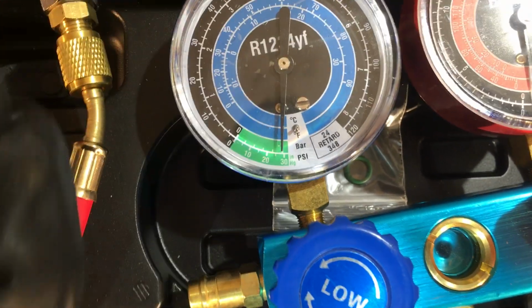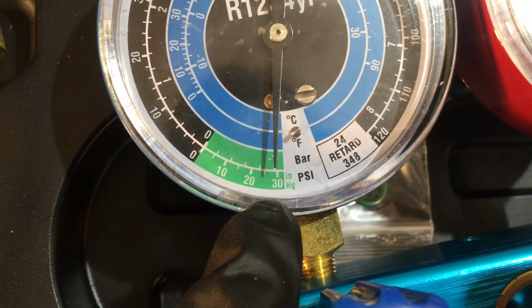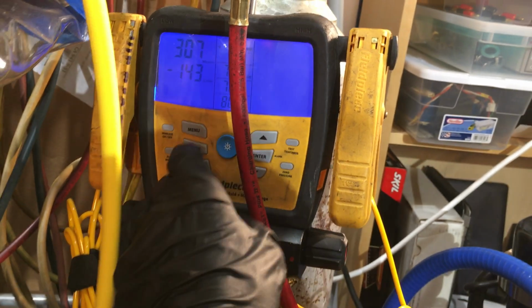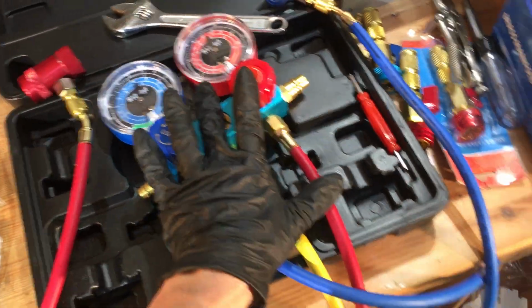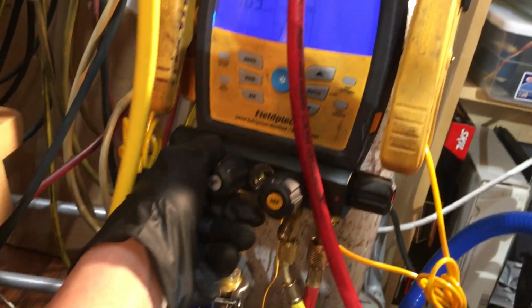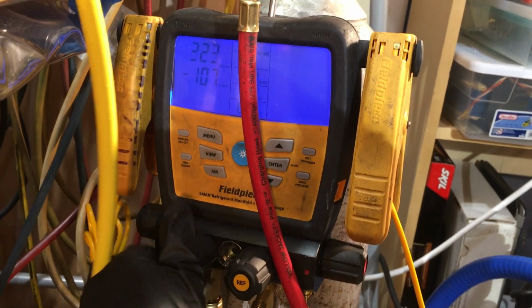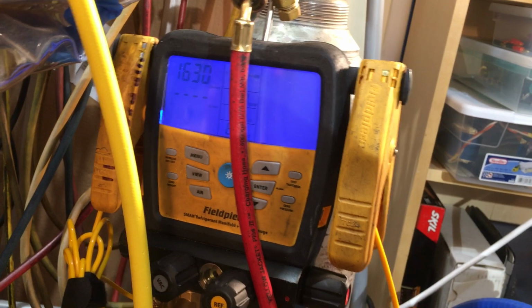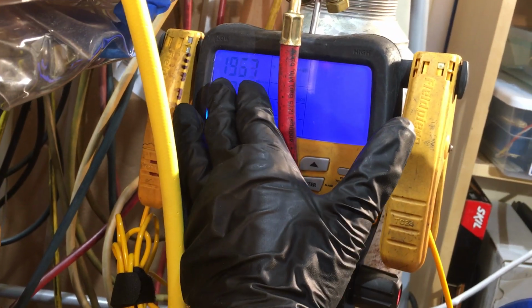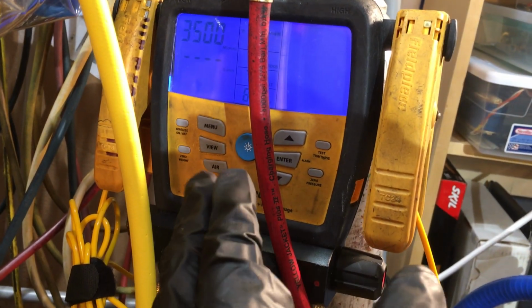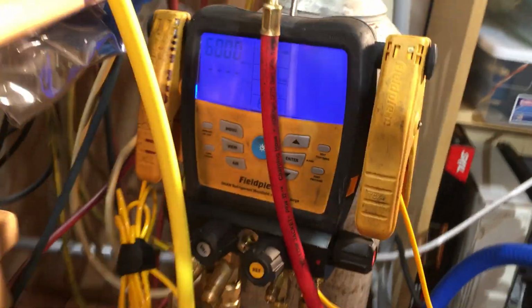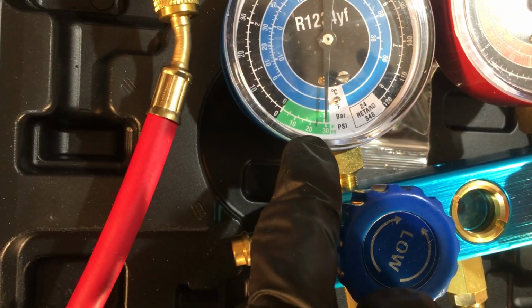We could almost say that's a 29. We're a little past 29. We're down to 300 microns. So now let's turn off the vacuum to these. So now I'm going to turn off my vacuum supply. And instantly we're jumping back up. Now if there's not a leak, it will stop, say at 3,500 or so. Oh, it's still going now. 5,000 microns, 6,000 microns. But if you see here, you're still at 29. You cannot see that leak on the gauge. 29.9, and it stopped right about there.